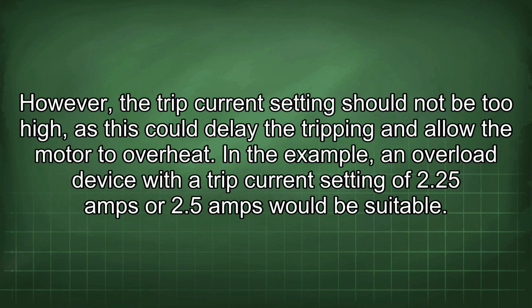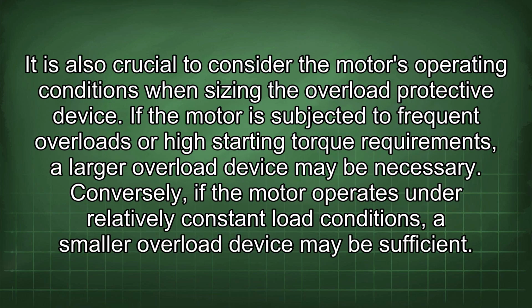It is also crucial to consider the motor's operating conditions when sizing the overload protective device. If the motor is subjected to frequent overloads or high starting torque requirements, a larger overload device may be necessary. Conversely, if the motor operates under relatively constant load conditions, a smaller overload device may be sufficient.